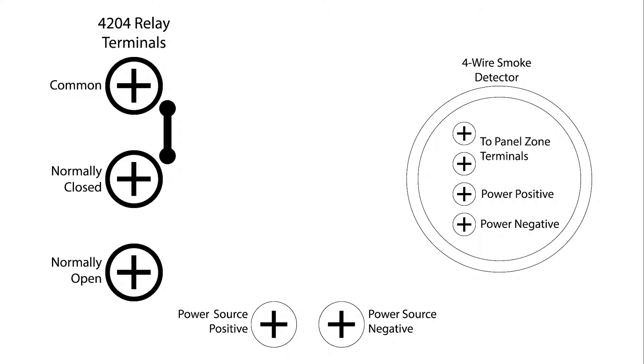Before we finish this video, I want to cover using a relay for smoke reset. This is a common use for relays when you need to drop power to a 4-wire smoke detector so that it can reset after an alarm. Let's take a look at the wiring for a smoke reset.